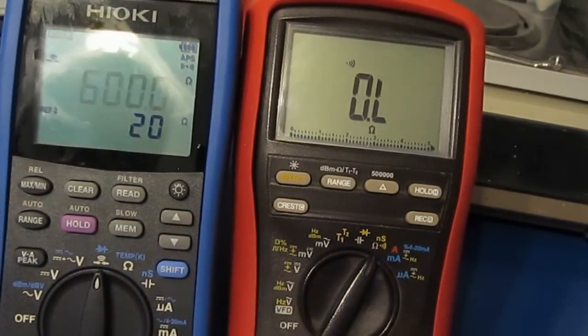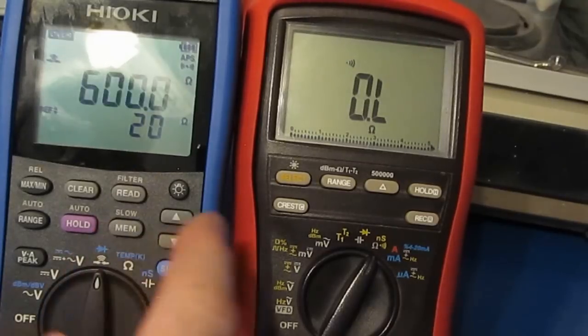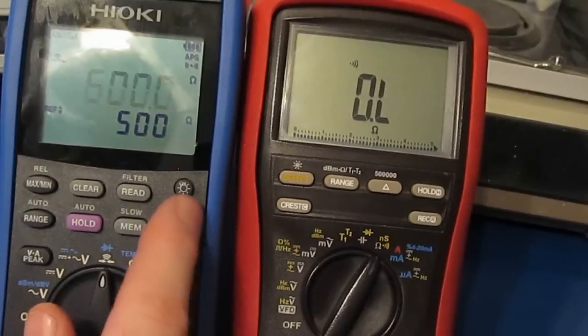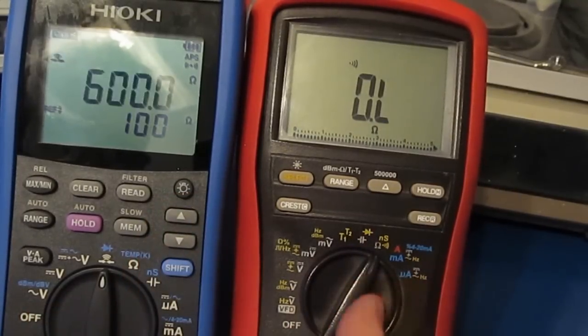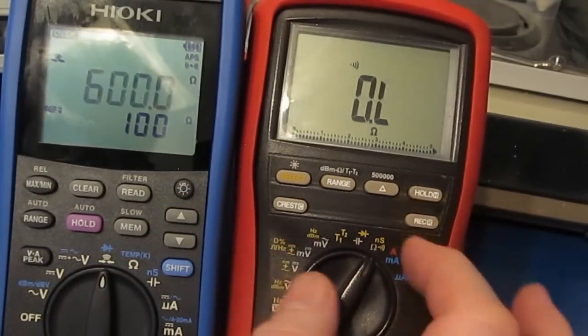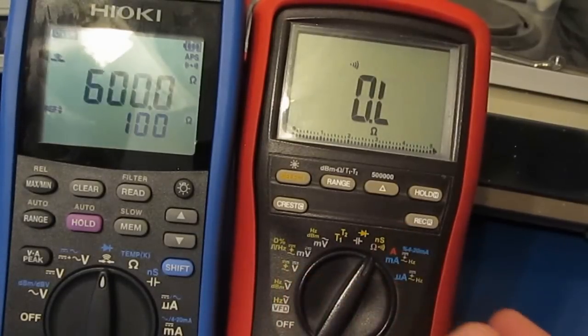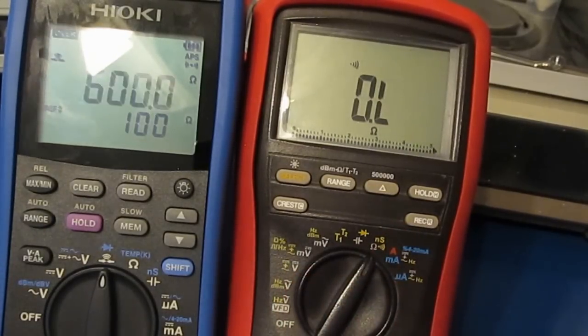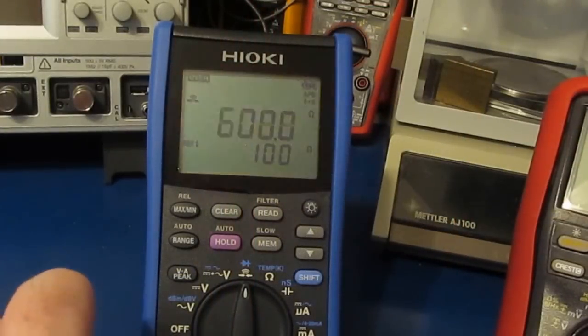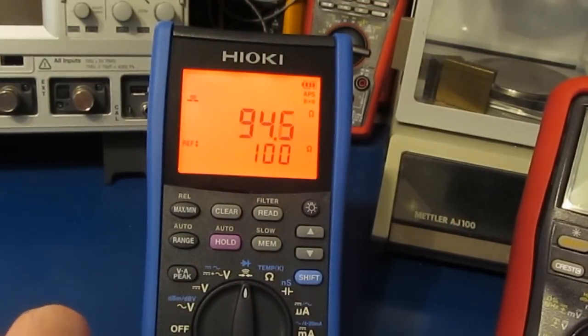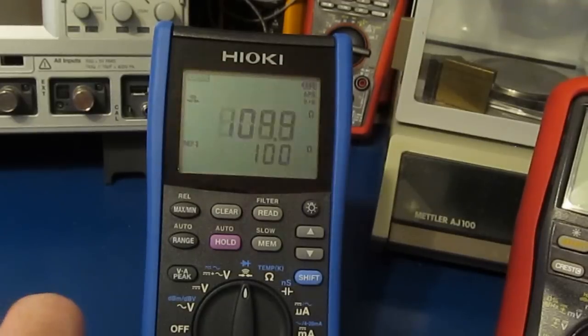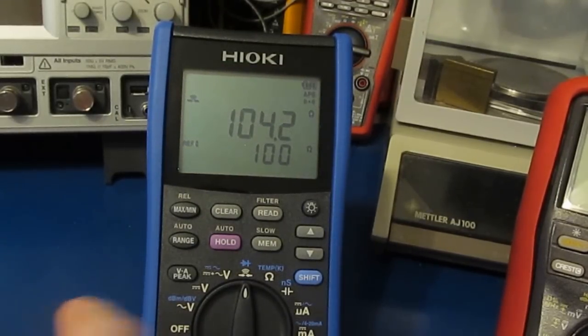But it's interesting, I believe you can program the threshold of this - there's 20, 50, 100, 500 ohms. And again, that's not programmable with the Brymen, that's a fixed resistance with this meter. Let's just see if that's really the case. Here's 70 ohms, here's 94 ohms, and you can see we're picking that up just fine. Let's go up another 10 ohms, and you can see it's no longer tripping.